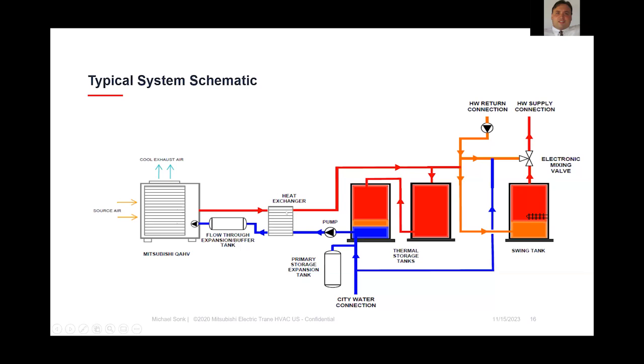So between the outdoor unit and this indoor heat exchanger, we're going to have a closed hydronic loop. This loop would have all the typical accessories and components that any conventional closed loop system would contain: air separators, expansion tanks, pressure reliefs, flush fill valves, things of that nature. We'll show some of those details further on in the presentation. And then indoors, where that heat exchanger is located, there would be an additional variable speed hydronic pump that is required to circulate cold water from the storage tanks through that heat exchanger to pick up the heat that the heat pump produces and then send it out to that storage tank farm.